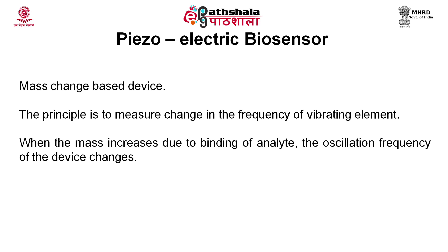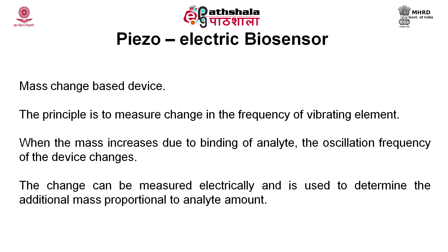Next, we will discuss piezoelectric biosensors. These are biosensors based on change in mass at the sensing platform. The principle is to measure the change in mass or the vibrating frequency of the element. When the mass increases due to the binding of the analyte — for example, the interaction of antigen and antibodies — the oscillation frequency of the device changes, which represents the concentration of the analyte. The change can be measured electrically and is used to determine the additional mass, which is proportional to the analyte amount.